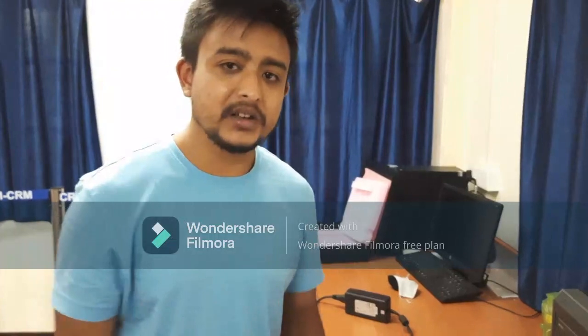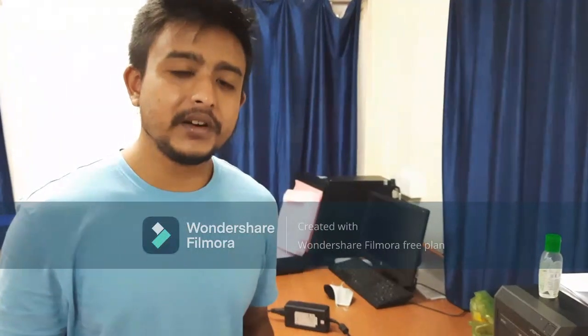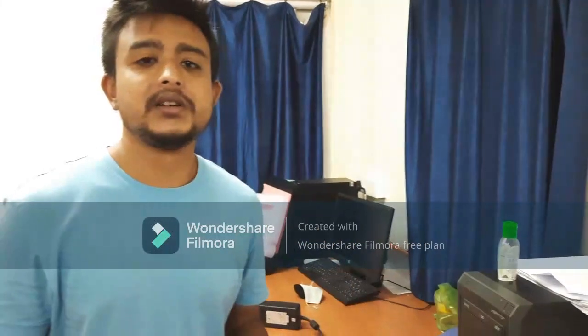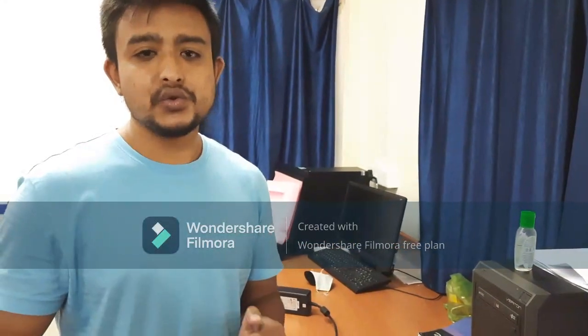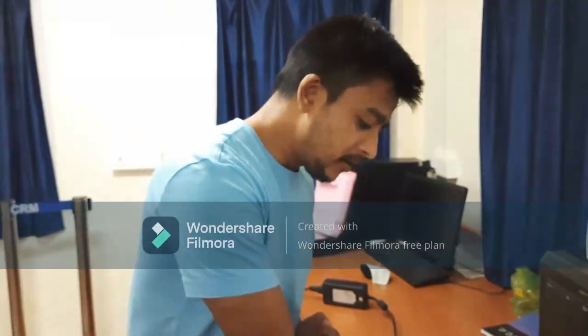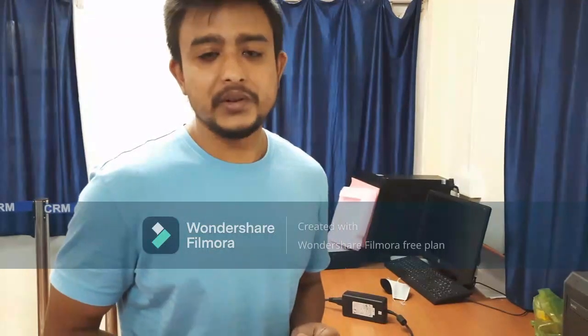From the graph we took the deviation and the gain, and put the deviation and the gain value in the calibrated section. We have calibrated the software, and after calibration it is automatically detecting. My last value was 105 degrees. I have not changed it, and once I put the slope value and the offset value, automatically it is detecting 106 degrees. There will be some slight deviations because we are moving it manually, but we are getting somewhat near to the exact measured value. Fine. So this is the end of the experiment.